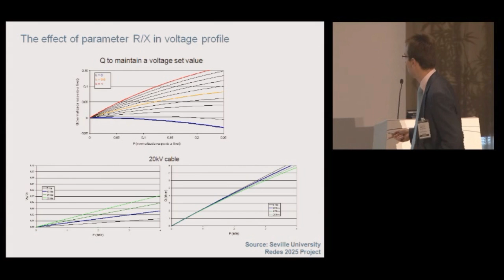Look at this example. Here we have a 20 kV cable, and this is the voltage variation when we are injecting active power. And here we have a graph that is telling us how much reactive power we have to inject when we are also injecting active power in order to maintain the voltage. So when we are injecting, for example, 4 megawatts of active power, we are going to need double of reactive power to maintain the voltage.